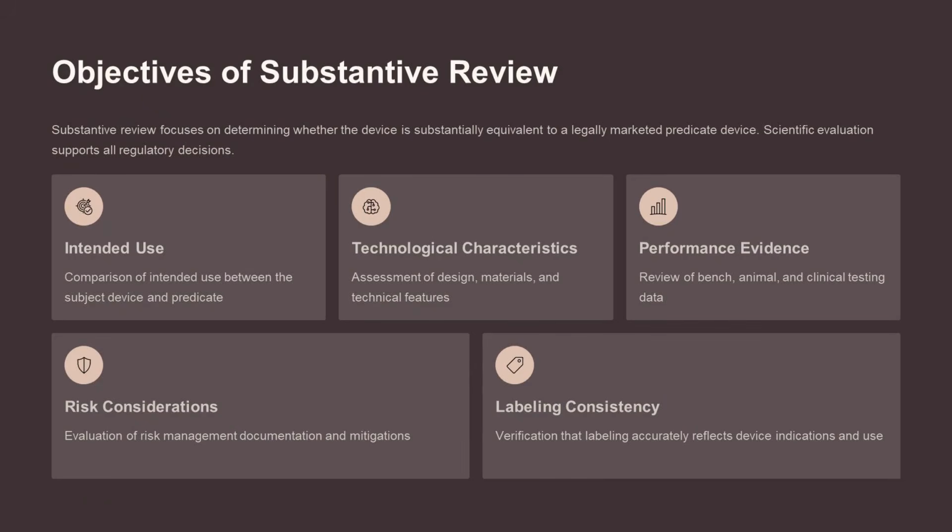Substantive review focuses on determining whether the device is substantially equivalent to a legally marketed predicate device. Scientific evaluation supports all regulatory decisions. The objectives include evaluating intended use, technological characteristics, performance evidence, risk considerations, and labeling consistency.